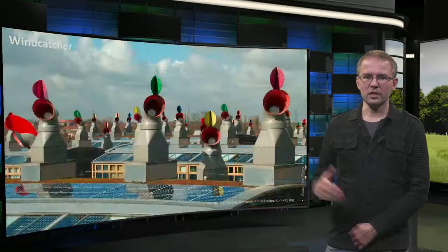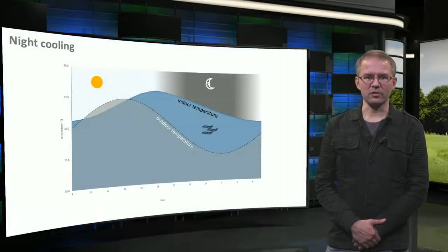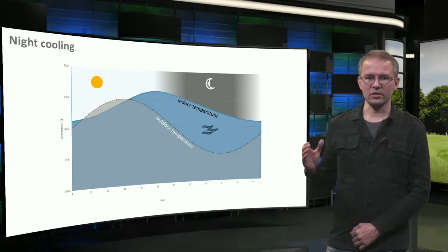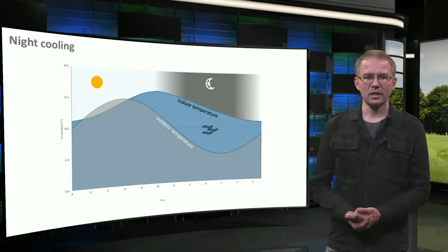This wind cowl is a modern example, used in the BedZED housing development in the UK. It automatically rotates with the wind. Night ventilation cools down the building at night so it can absorb more heat during the day. This example shows the effect of just using night ventilation — the mass of the building has cooled down so much that it takes several hours for the indoor temperature to catch up. Night ventilation does require building mass, so it will not work very well with light structures.